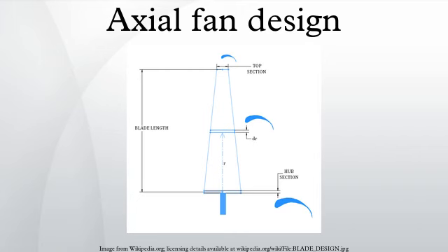efficiency. An axial fan consists of much fewer blades, that is, 2 to 6, as compared to ducted fans. Axial fans operate at high specific speed, that is, high flow rate and low head, and hence adding more blades will restrict the high flow rate required for its operation. Due to fewer blades, they are unable to impose their geometry on the flow, making the rotor geometry and the inlet and outlet velocity triangles meaningless.